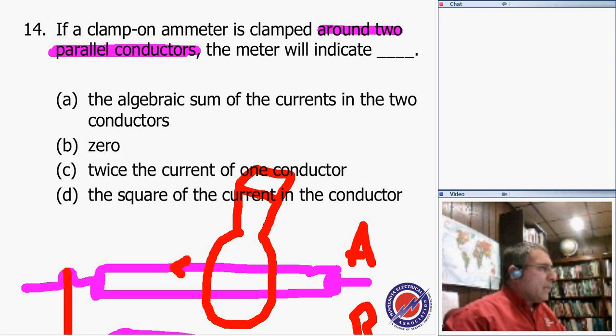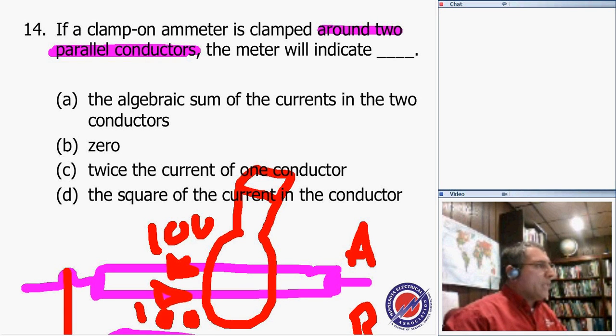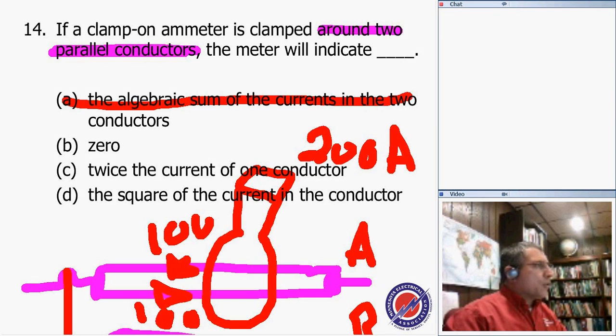If there is 100 amp here, and also the other way around, it should go right there. And there's also 100 amp in this one, so the total, guys, will be seen here as 200 amp, right? Because they're the same phase in the same direction. Now, that's probably a lot of you guys, so it measures the algebraic sum of the currents in the two conductors. So if there's 100, it will measure 200.